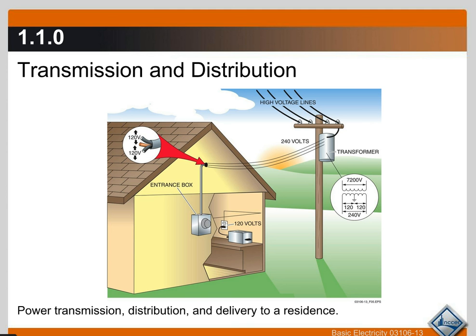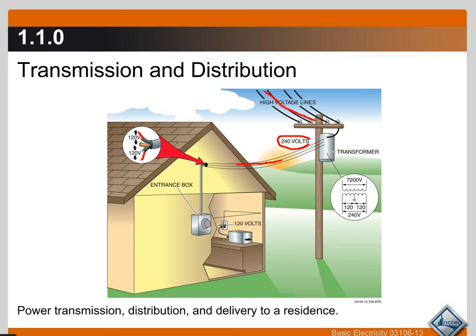The high voltage lines come into the transformer out on the pole, which steps the voltage down to 240 volts. That feeds through our service line into the house on two wires — 120 volts on one wire and a different phase of 120 on another. Don't worry about phases right now; just know it comes in on two lines at 120 each into the entrance box, then distributed throughout the home. Standard plug-in outlets for TVs and toasters are 120V; electric water heaters, air conditioning condensing units, and compressors use 240 volts.